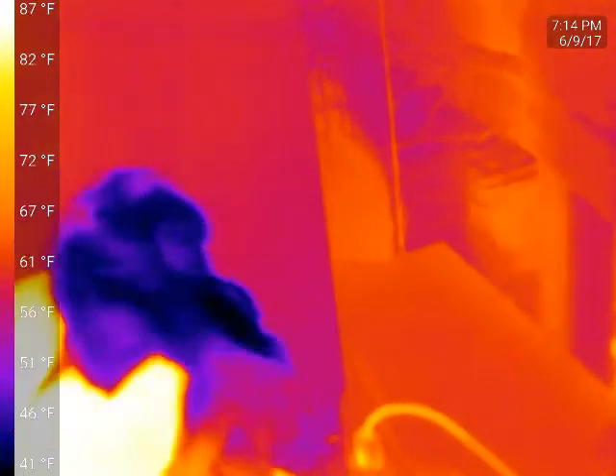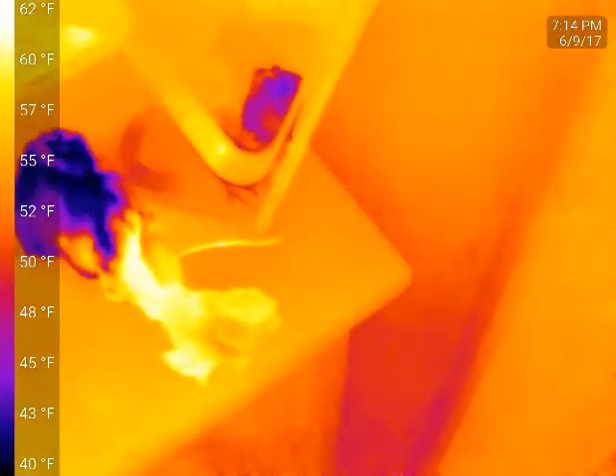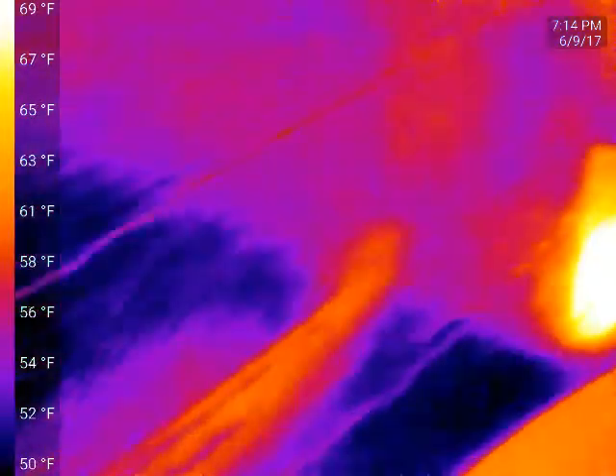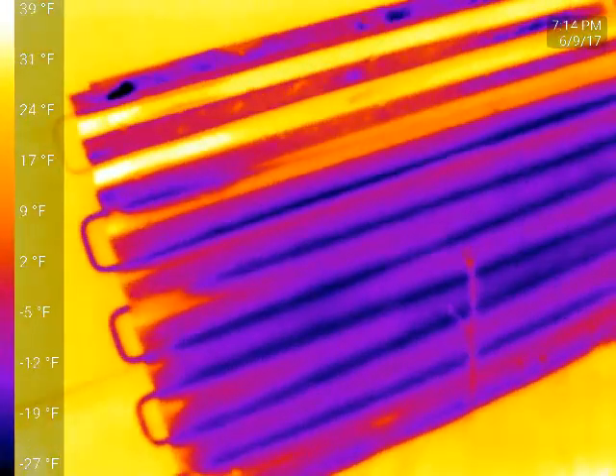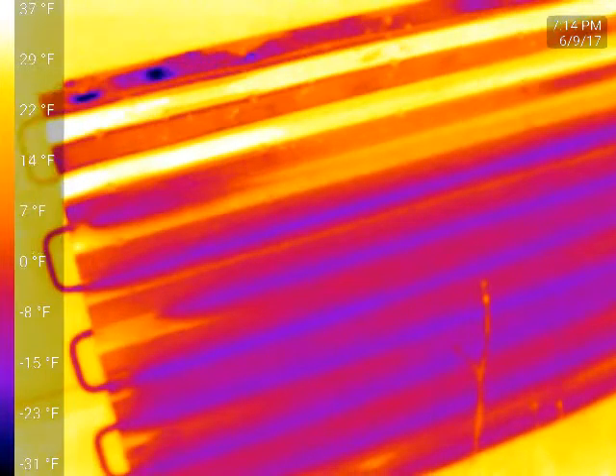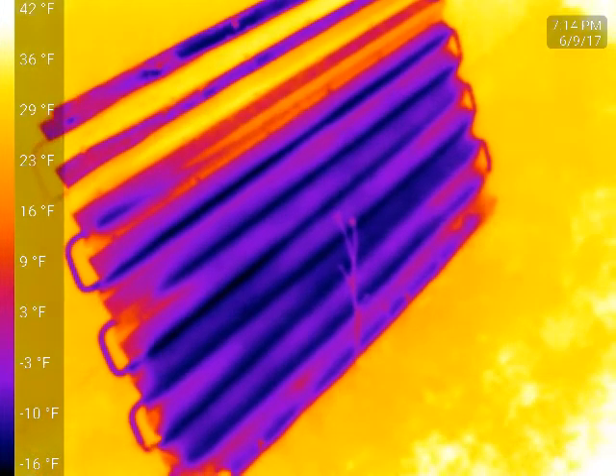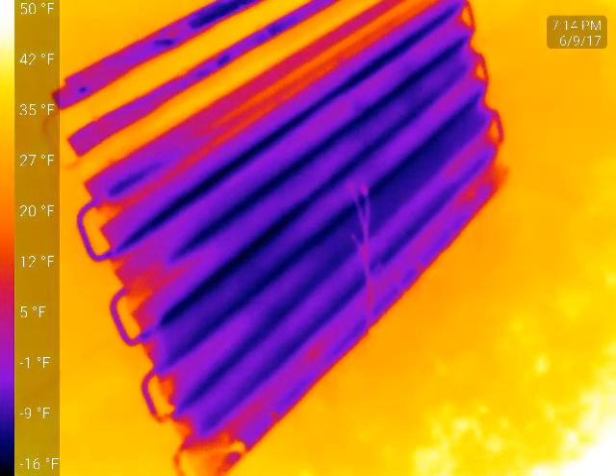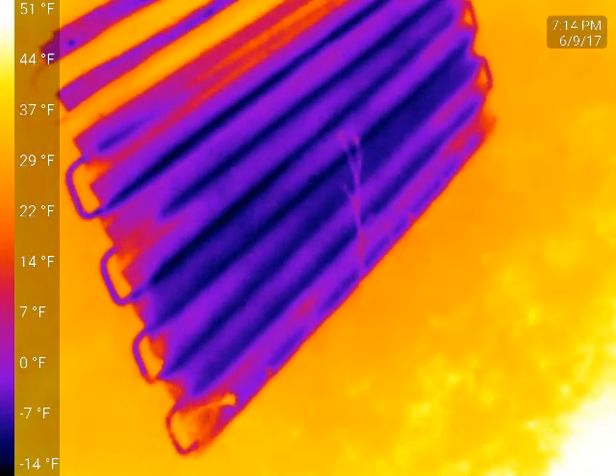I was cleaning a little bit earlier, just wiping some dust and a little bit of blue paint off the side with alcohol. I built this heat pump last fall, just slapped it together — pretty cheap, didn't put a lot of thought into it, including the evaporator. As far as just throwing it together, it held charge really well — only two flare fittings. I'm pretty happy that it runs propane, just like everything else I've built.